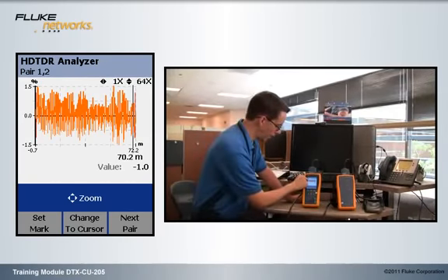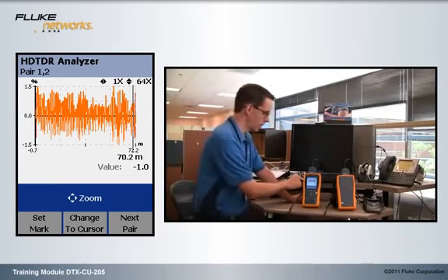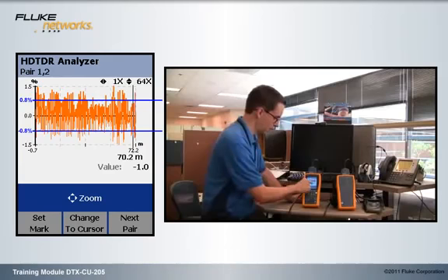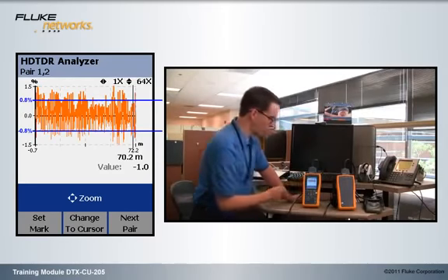Remember our rule from the previous modules? We don't want more than 0.8% or minus 0.8% in the cable, which is roughly halfway up the scale here. Let's put in those 0.8 and minus 0.8 lines now. We're going to put them in here and here. And we can see that pretty much all the way down the cable it's exceeded our 0.8 and minus 0.8%. Sure, you're going to get a couple which exceeded, that's normal, but look at how many, the density of what's going on. We definitely have a cable issue here.